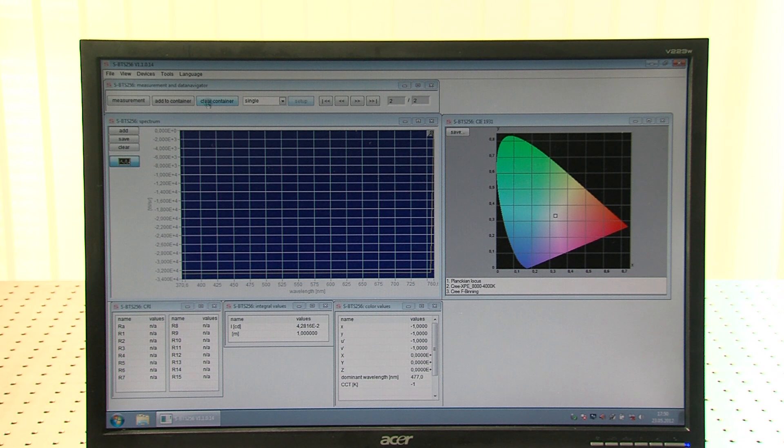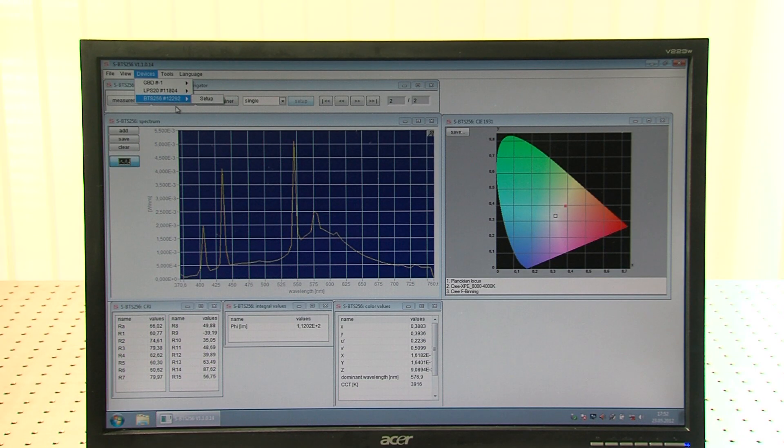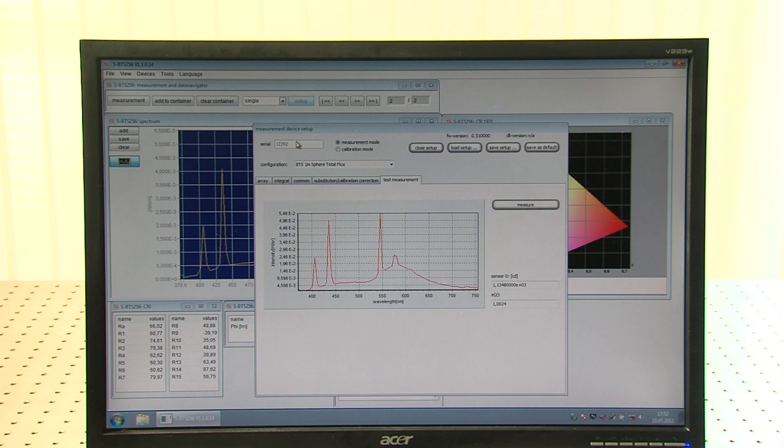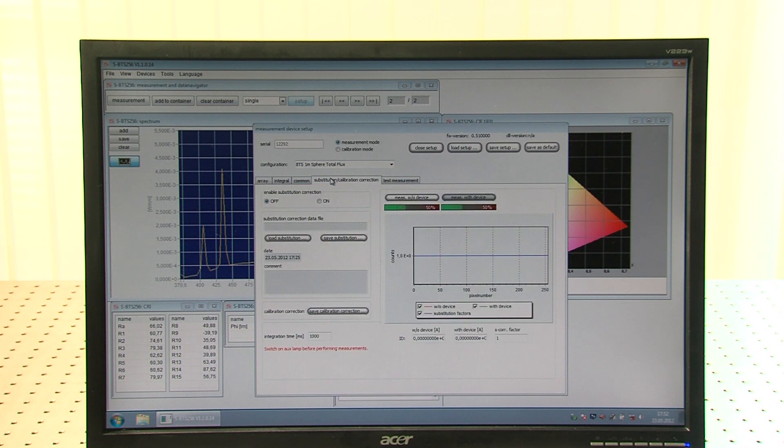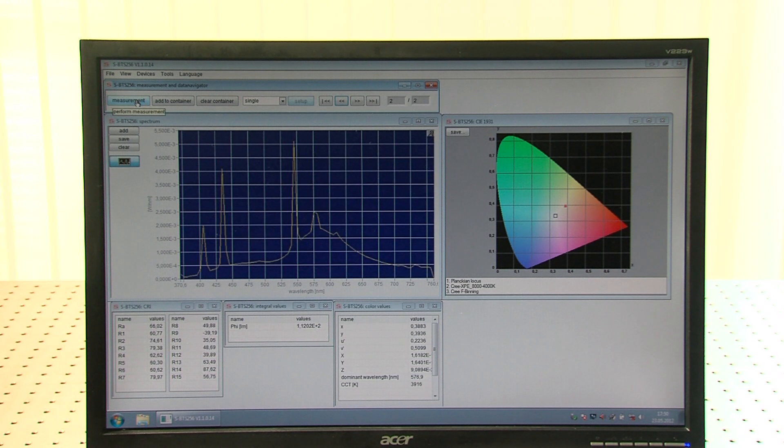Select the BTS-256 with external integrating sphere in the configuration area of the desktop. The software provides a routine for correction of self-absorption errors using the auxiliary lamp. In single measurement mode, a single reading is made once the test source has stabilized. Measured values are displayed on the desktop in the appropriate windows.